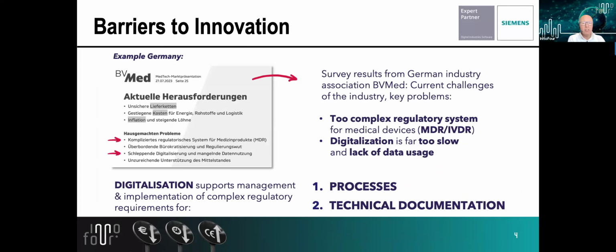In Europe, due to an extensive change resulting from the MDR and IVDR, a new market approval is required for all medical devices and in vitro devices, IVDs, already on the market, which means a revision of the technical documentation for each of these devices. The Medical Device Regulation, MDR, came into effect in May 2021, replacing the old MDD, Medical Device Directive, and the in vitro diagnostic device regulation, or IVDR, came into effect in May 2022, a year later, replacing the in vitro diagnostic medical device directive, IVDD.